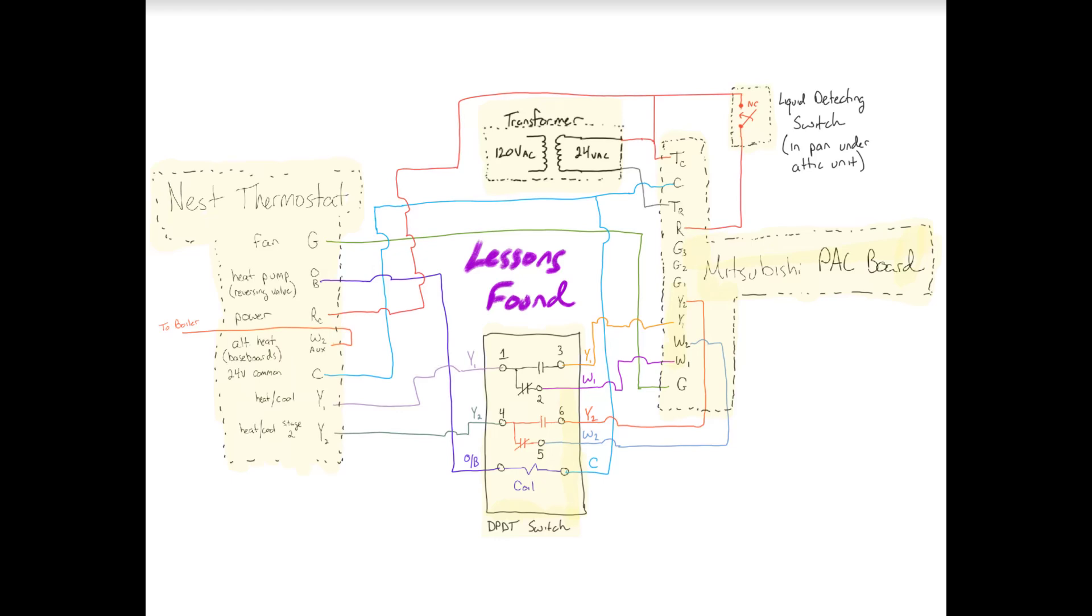Okay, so now let's look at the common. So that's that blue line right in the middle of the screen. You'll see the 24 volt common on the Nest thermostat. It connects to the C on the Mitsubishi PAC board, and it also connects to the other side of the double pole, double throw switch. So that's going to be the bottom of the double pole, double throw switch on the right side.